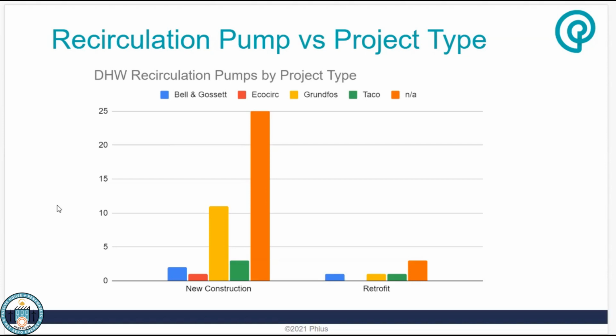trying to meet this time to hot or reduce the amount of wastewater in those projects, a lot of times they're turning to these recirc pumps to meet that testing requirement. So that's kind of why we see not as many not applicables in the retrofit categories as we do in new construction, when you can actually design your system where your piping is closer to the fixtures.